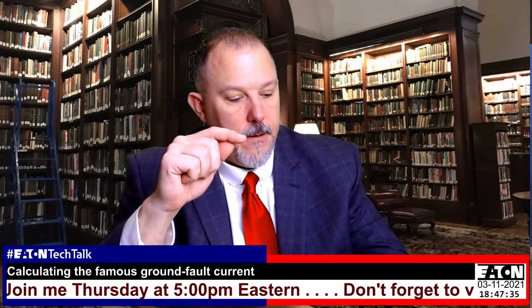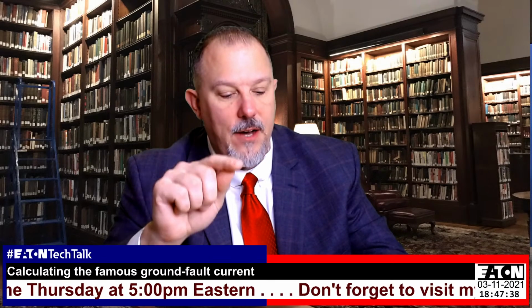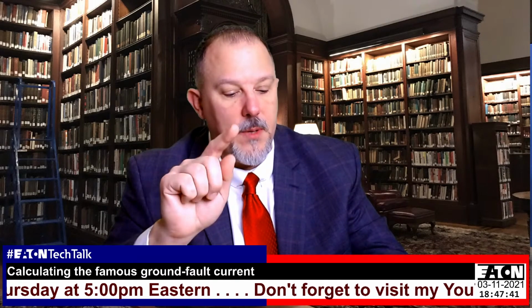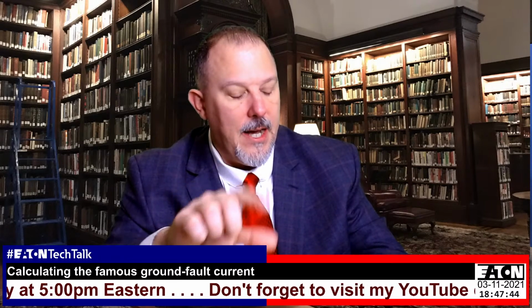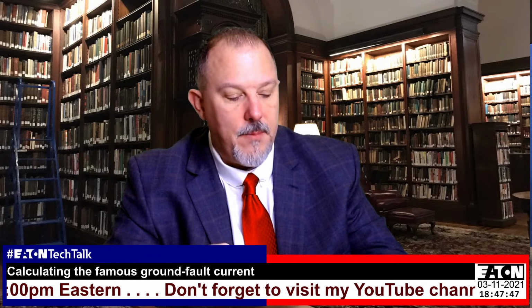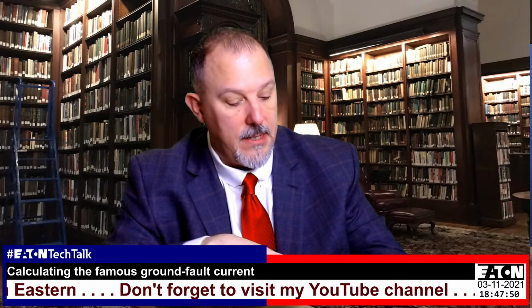So it gets a little bit more dicey when you're dealing with conductors. It says it's apparent that no precise calculated value of ground return impedance is to be expected because of varying ground conductivity. However, a satisfactory determination can be made by a combination of test procedures and theory. He's got a big, long impedance calculation in here, and they talk about the height of the conductors off the ground. So it tells me there's probably some complicated math behind SKM and why they use what they use.